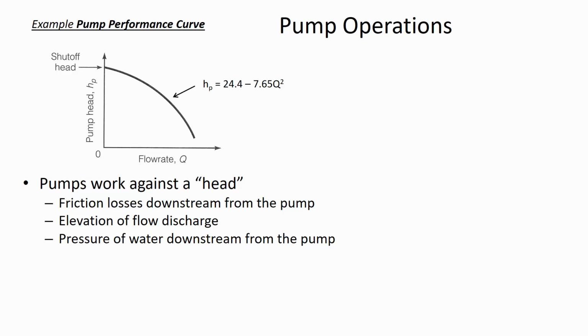The pump head, one way to think about this is that the elevation that it has to lift the water can be no more than the pump head. And this is sometimes called the shutoff head. It's marked on the figure here because if the pump is asked to add more head than this vertical intercept, then it achieves zero flow rate. But if I combine a certain pump with a system that has maybe just a little bit of friction, then it wouldn't need to add very much head. So I may be lower down on here, and so it would achieve a really high flow rate.